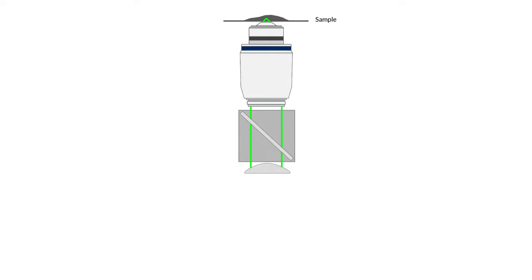Remember that it contains signal from all focal planes within the laser's tiny spot of illumination. A confocal microscope will then take our emission signal after the dichroic, and focus it onto a conjugate focal plane close to our detector. A conjugate focal plane is an intermediate image plane that focuses to the same spot as the objective. It's in this conjugate focal plane that we can insert our pinhole. If we close down this diaphragm to the focal point of the lens, we only allow signal from the plane that is in focus for our objective to get through to the detector.